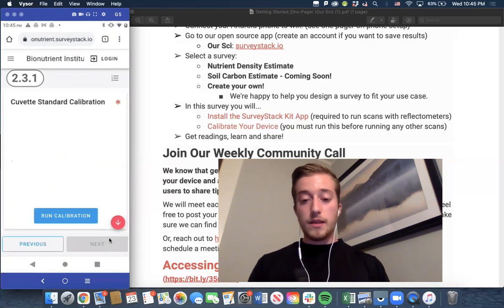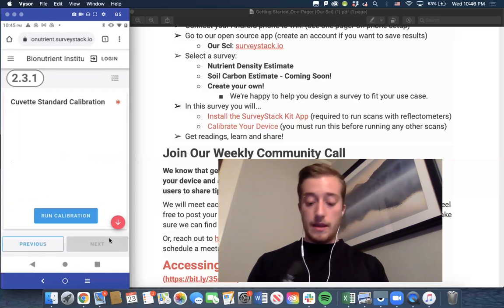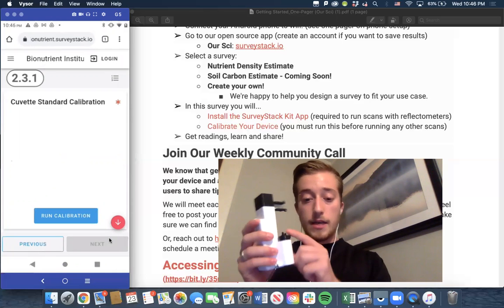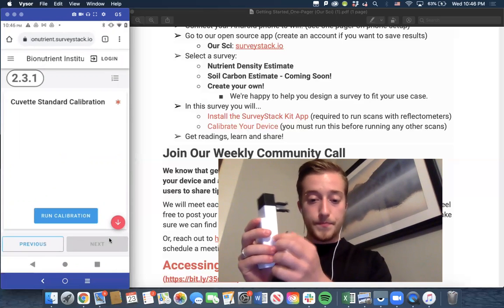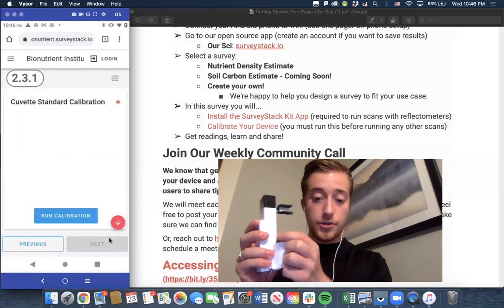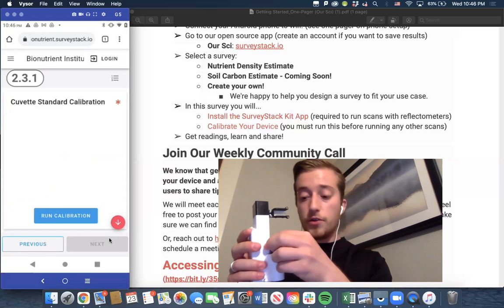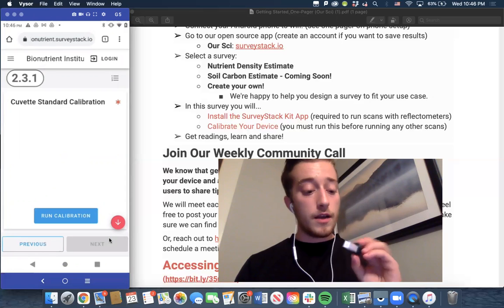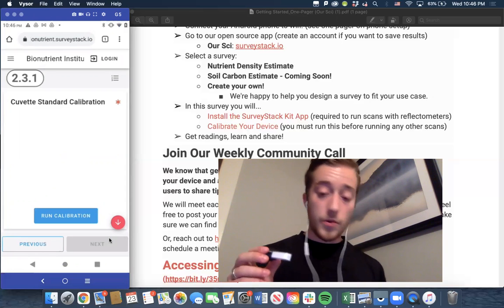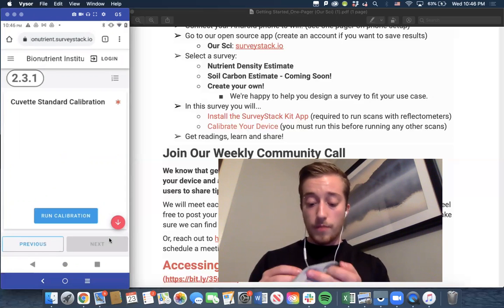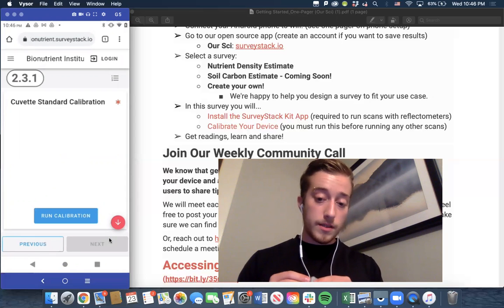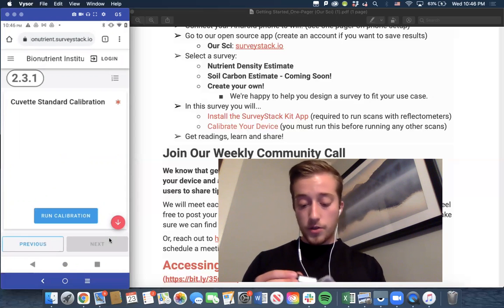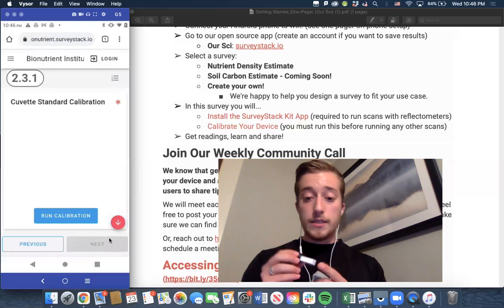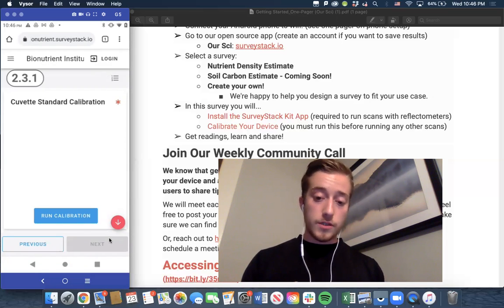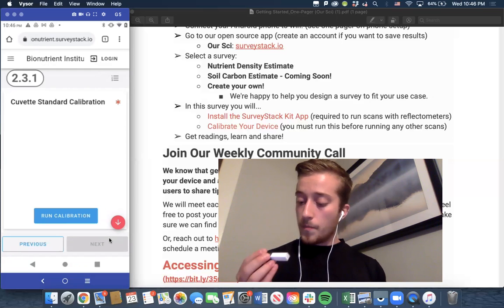So this is the most reflectant thing that your device should encounter, and you'll see here a piece that's screwed in. You should unscrew that. This is your cuvette standard. It's your calibration standard. Each device has its own unique calibration standard. You can read more about how we calibrate these online on our tutorials, but you need to keep this. If you lose it, we would have to intake the device and assign a new calibration standard. It's not a step that can be done at home.